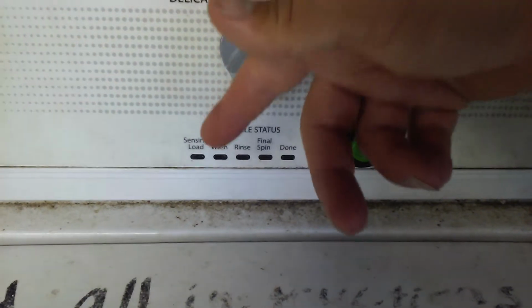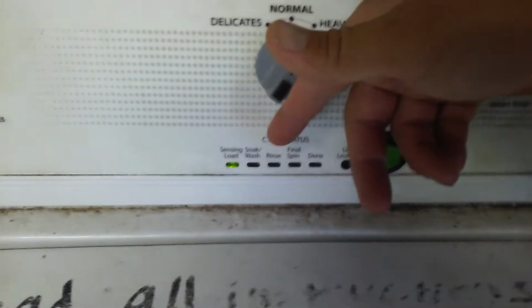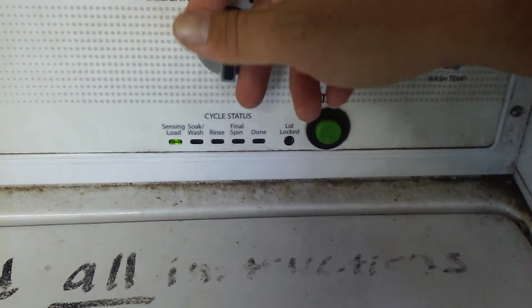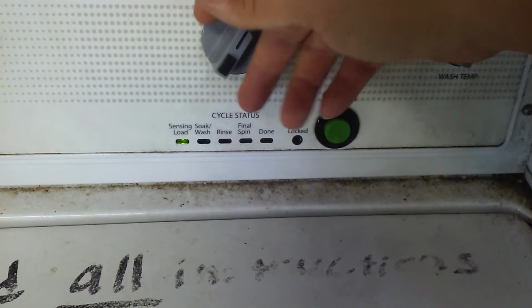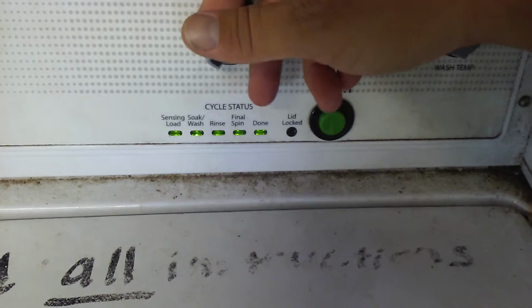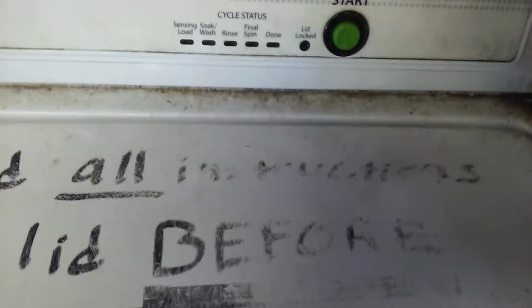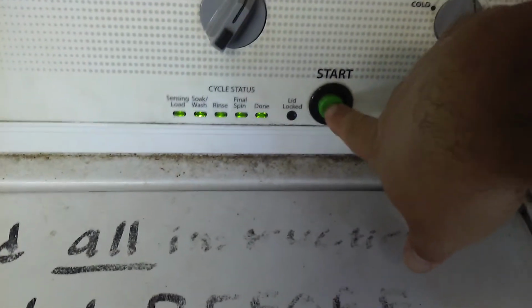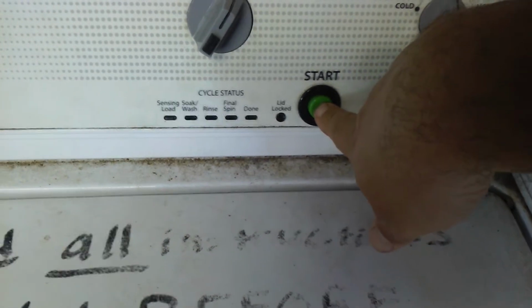Let's go ahead and do a cycle. See, now it's flashing just that one. That means there's nothing, no codes available. So my codes read F0, E0, no fault, and it's going to show 4 of those. 1, 2, 3, 4. And we're back at the beginning. So let's go ahead and do the long hold to exit out of the system.